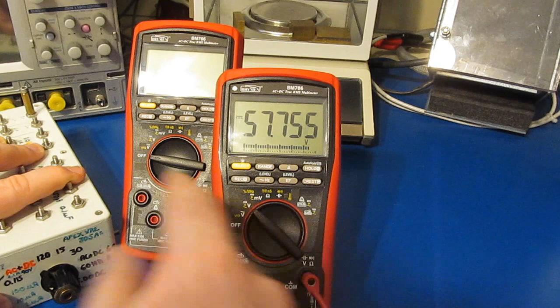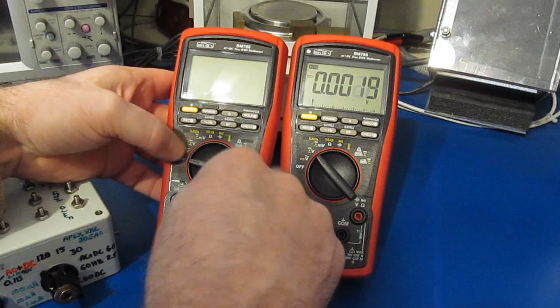Let's have a look at our original meter and let me show you the problem. If the meter's in DC voltage mode connected to our test box, and we put out 5 volts DC, the meter doesn't have any problems with that. But let's go to this high voltage square wave, roughly 60 volts or so, and you can see the meter reads basically 4.5 volts. If we manually range the meter, you can see it reads roughly 58 volts. And if we go back to auto range, take away the voltage and reapply it, it goes back to 4.5 volts.